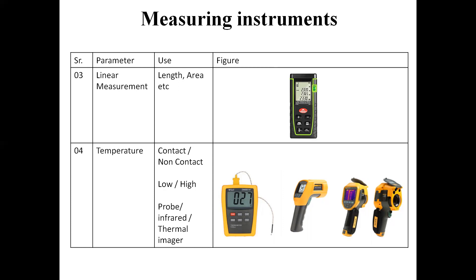For temperature measurement, there is a contact type, a non-contact type, a probe type, an infrared type, and a thermal imager type. The first is the contact-type low-temperature probe — you can directly place the probe on the surface of the instrument to get the temperature. This instrument is used where the temperature is not more than about 200–250 degrees Celsius. It is dangerous to use a contact-type instrument at temperatures exceeding 300 degrees.